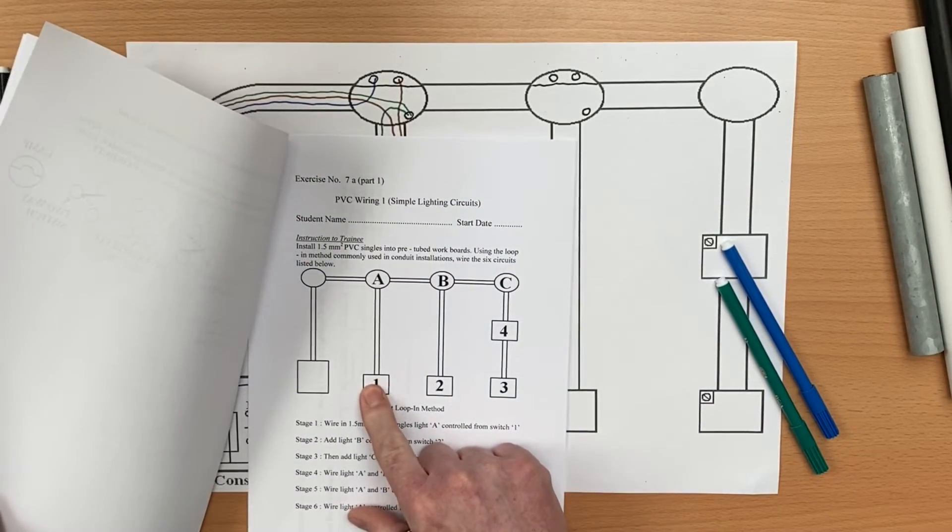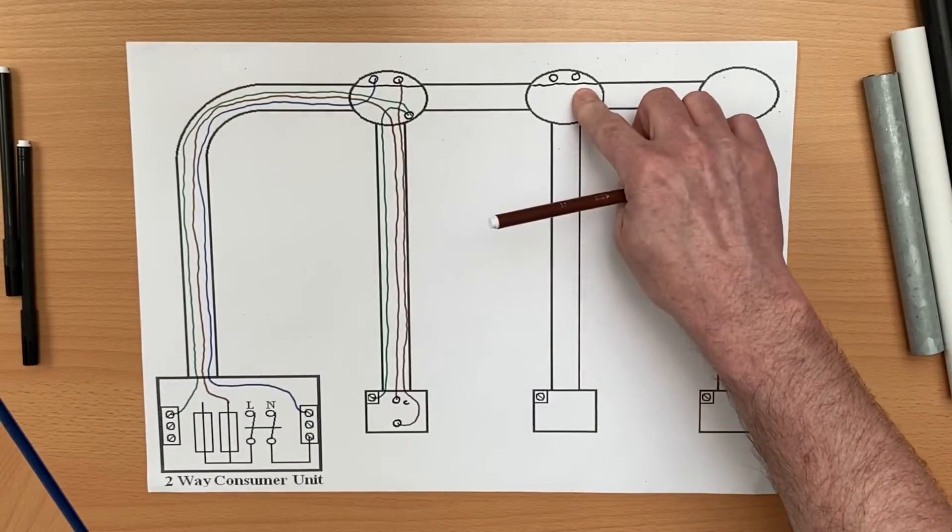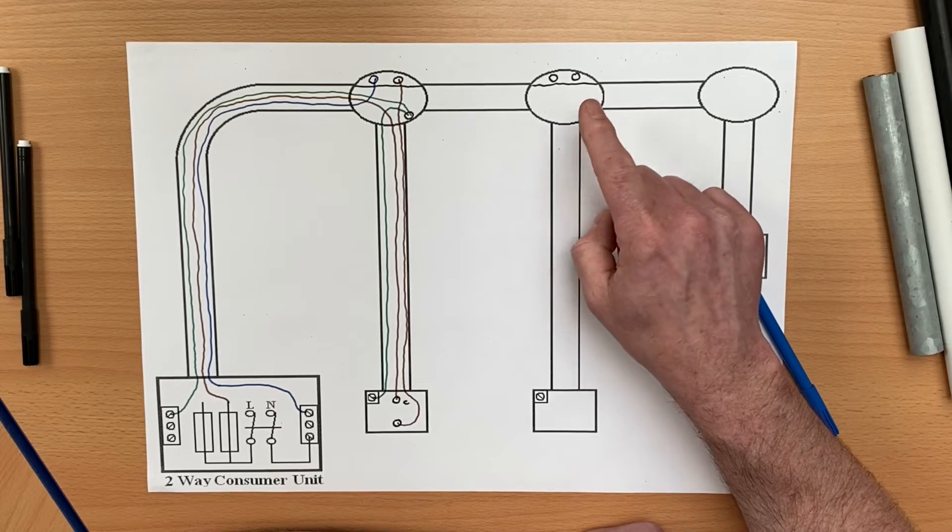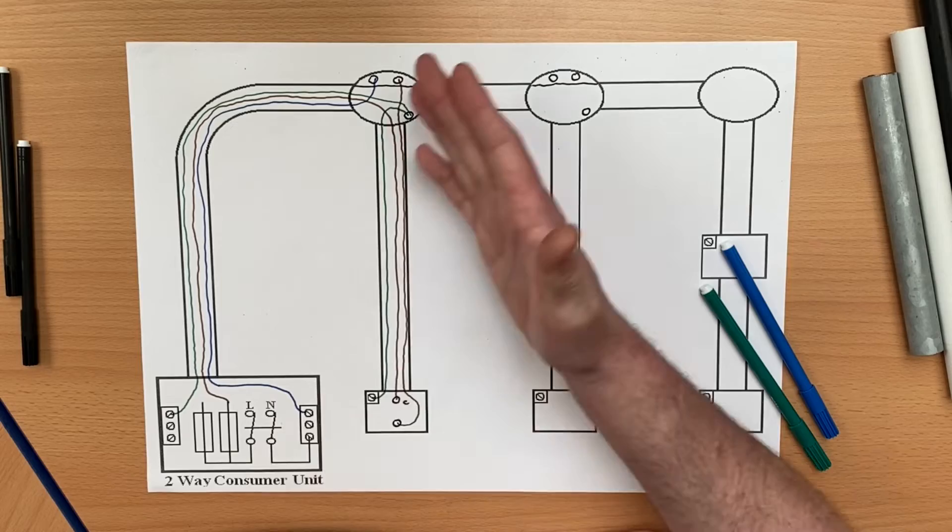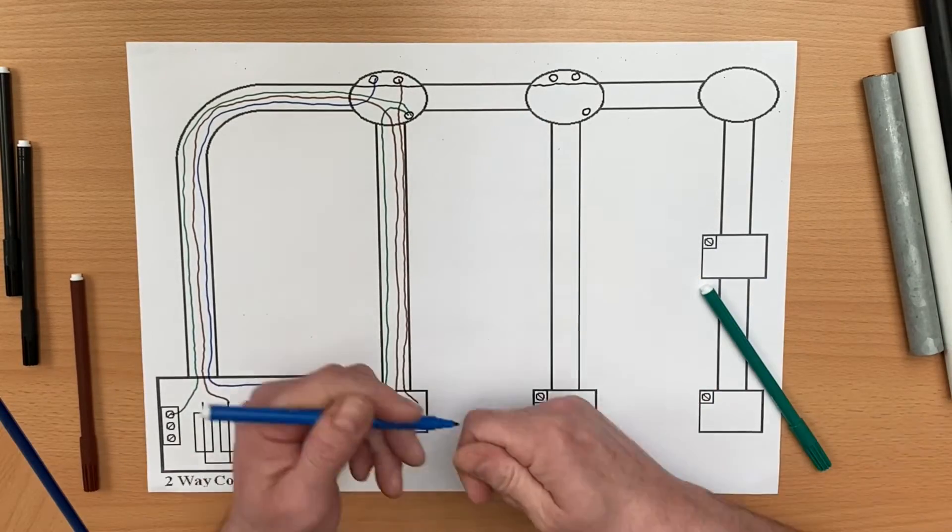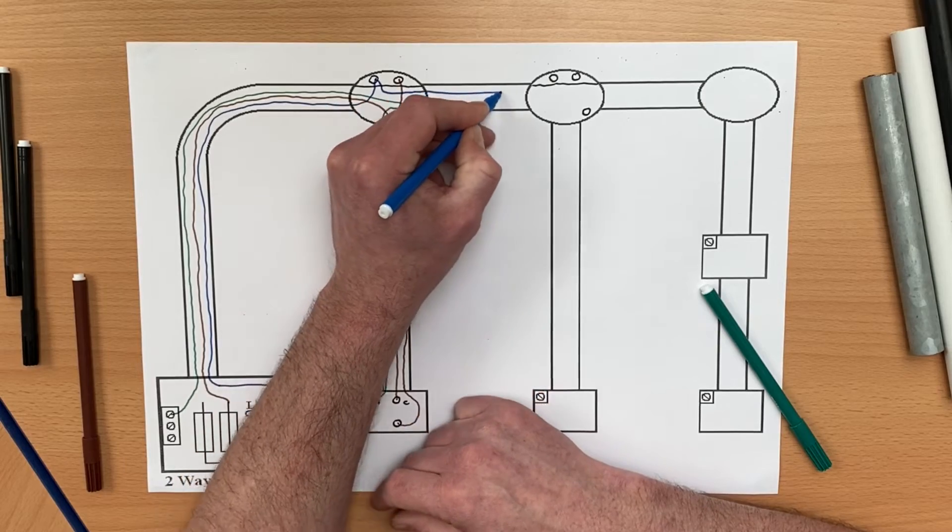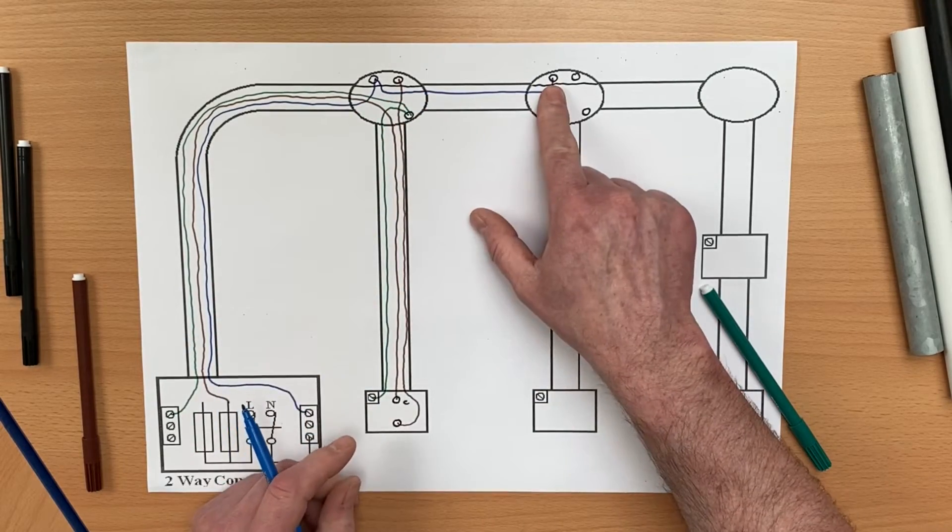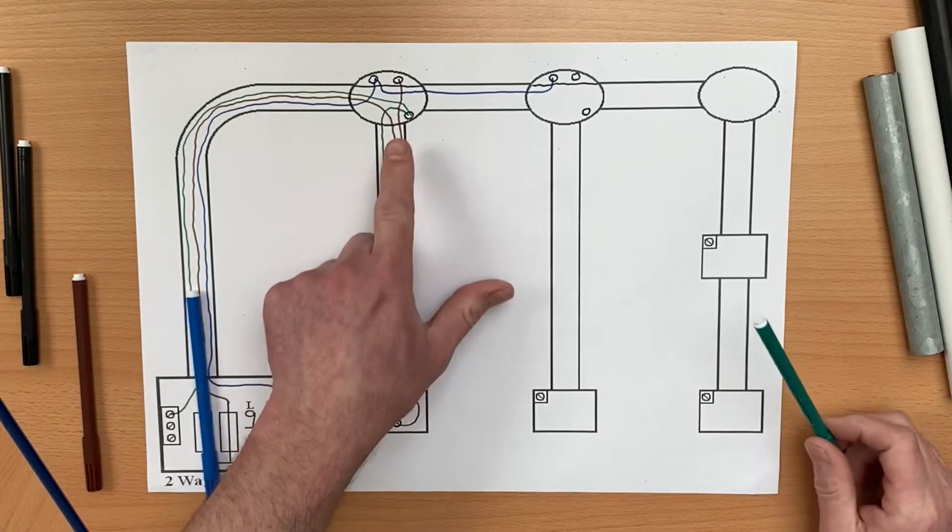However, for stage 4 of your practical exercise book, which is in here, stage 4 requires this switch to turn on two lighting points. So this lighting point here will need a neutral, a CPC, and the same switching line conductor that this circuit had. Let's start off by doing the neutral. We're familiar with the fact we take our closest neutral, so we take a neutral out of here in PVC singles and we drop it off there.